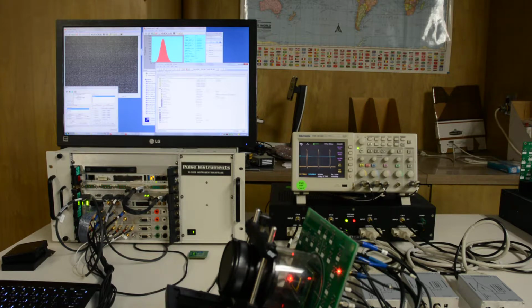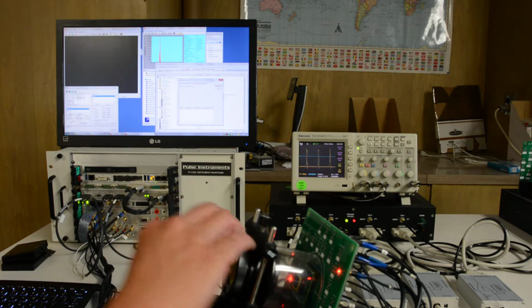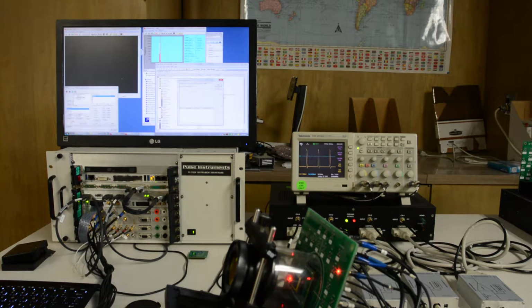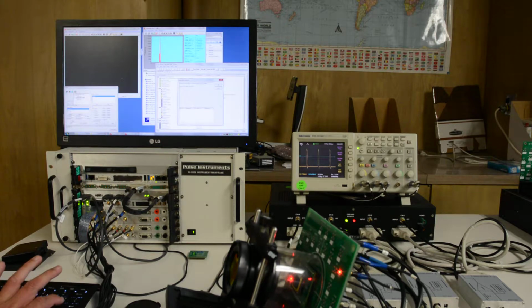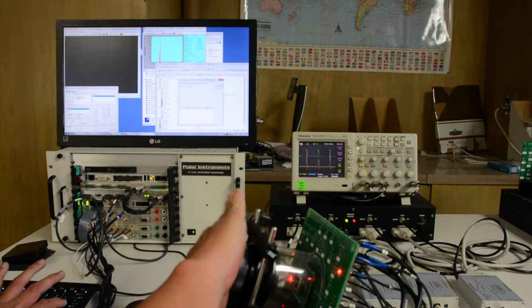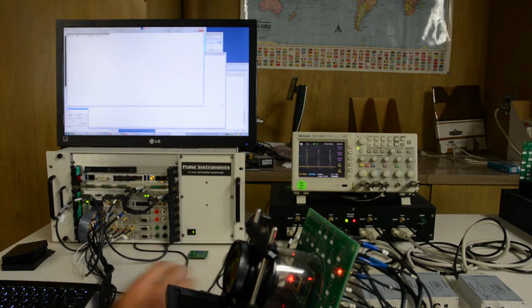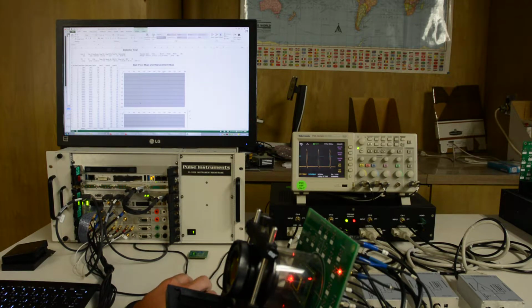It's going to acquire 50 frames for calculating pixel noise. The second sample it wants is a midpoint temperature for the residual non-uniformity calculation. I'm going to use the palm of my hand for the midpoint temperature. And for the hot temperature, I'm going to provide a slightly higher temperature and collect another 50 frames. It's going to take these data sets, perform some basic calculations, and produce an output report in Excel.